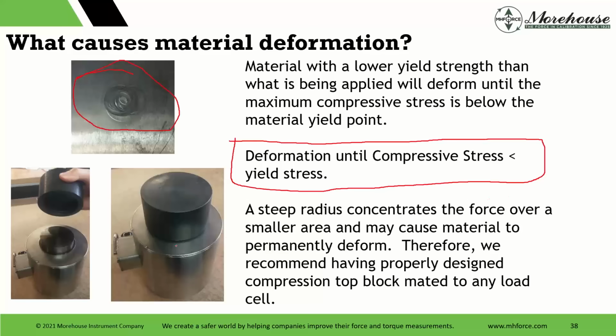What we do with our material here in the hard block, these are over designed for the most part. They could be a little bit less height wise, though we over design them intentionally. And the top block, a steep radius, concentrates the force over a smaller area and may cause the material to permanently deform. That is going to happen. Once you marry a top cap to the load cell, it's like anything else. It's married, it's there for life, hopefully. And if it deforms, that's fine. It'll deform with the load cell, and we have really made these a bit of overkill as far as the design, so they do not break, or hopefully they do not break.